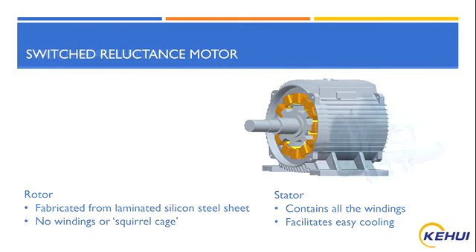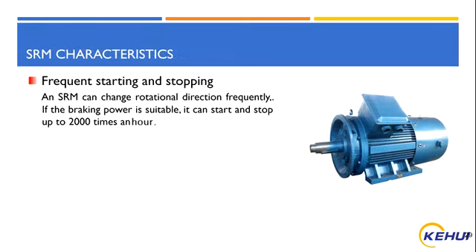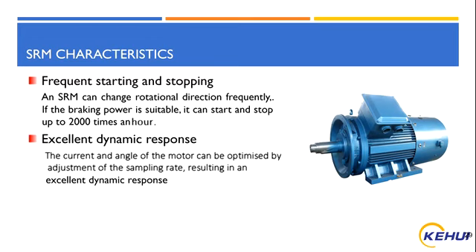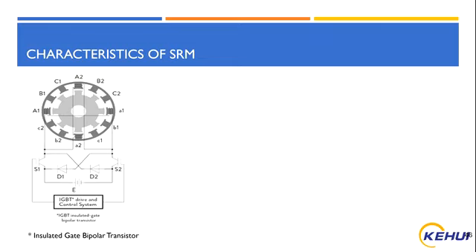The switched reluctance motor has the ability to change rotational direction frequently. If it has suitable braking power, it can start and stop up to 2,000 times in an hour. The motors can quickly adapt to changes in the load by adjustments to the sampling rate, thus giving them excellent dynamic response. Now let's take a look at how the system works by considering a cross-section of the motor and a simplified version of the control unit.